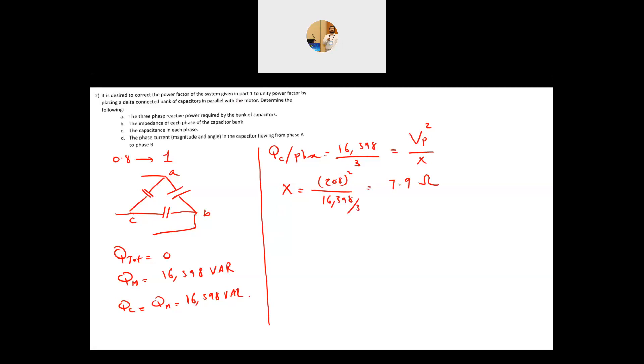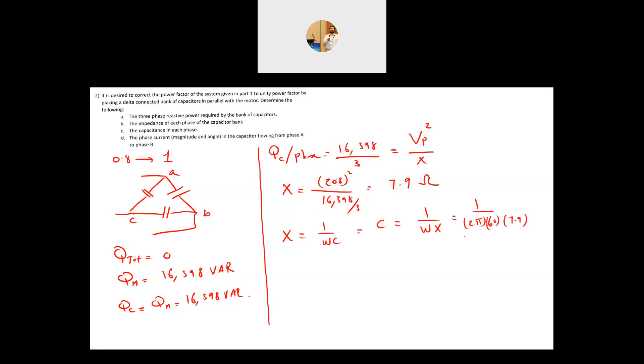To find the capacitance in each phase: X_C = 1 / (ωC), so C = 1 / (ω × X_C) = 1 / (2π × 60 × 7.9) = 0.000336 F, or approximately 336 μF. That is the capacitance per phase of the delta-connected capacitor bank.